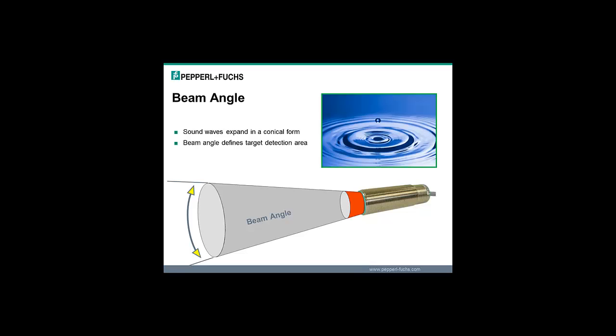The next topic to discuss is the beam angle. Just as when you talk, your voice kind of fills the entire room as you speak, ultrasonic sensors are also using sound, so their sound expands out in kind of a conical shape once that transducer is struck and the evaluation pulse is created. So that's something to keep in mind: it's not like a laser beam. The sound comes out in a wider area and you have a wider area of coverage for ultrasonics. And this beam angle is specified in Pepperl+Fuchs datasheets.